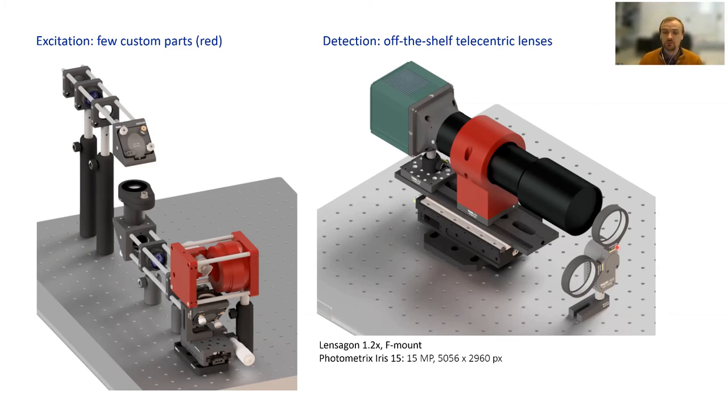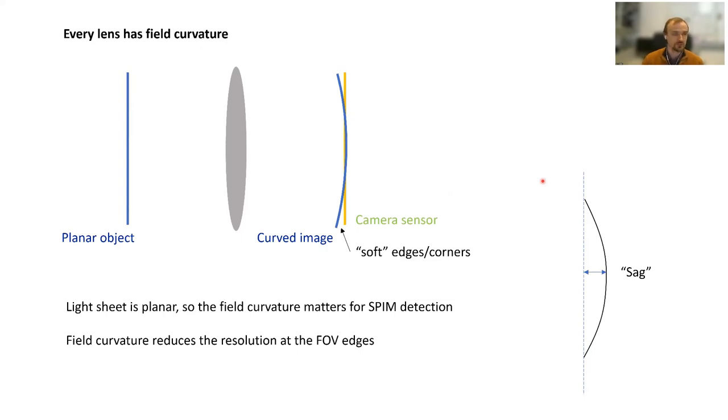Now the big question when we start switching the detection optics: which detection lenses are good? How can we make informed decisions about good or bad choices of the detection lenses? One characteristic of every lens is that it has field curvature. If you have a planar object, when it is focused, the image is always curved. This is true even for very high-end objectives and lenses. For light sheet microscopy this is especially important because our excitation plane is planar, so we want a planar image on the camera sensor. If it is curved, we will lose resolution at the image corners.